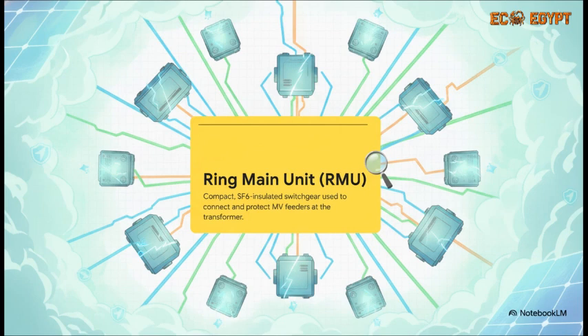And right alongside those heavy-duty specs, notice the universal green, red, and flashing amber color codes on the control panels. These mimic circuits give operators an instant, universal signal if a breaker is safely closed, open, or if a critical trip just happened. Right inside these stations is a crucial piece of hardware, the ring main unit, or RMU. Think of the RMU as the ultimate local bodyguard for your transformer. Since it's handling massive MV power, 33,000 volts, it uses a highly pressurized, sealed metal enclosure filled with specialized SF6 gas. This gas is an incredible insulator, letting the unit instantly extinguish dangerous electrical arcs in a fraction of a second, actively preventing catastrophic explosions right out in the field.